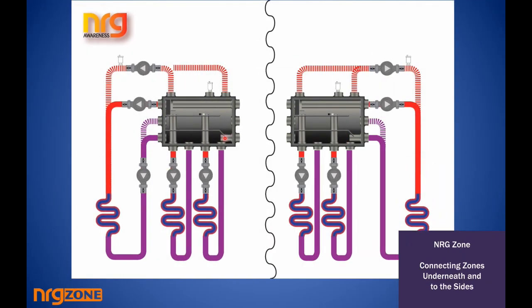So if we take it now that we have zones, if we have our heat coming in at the right hand side here into R1 and coming back from say R3, we can then take zones from this point over to a pump from T3. You could actually take it from T2 if you have a vent on T2, but you pump towards the vent, you never put the vent behind the pump. And you can also take it from T1 through a pump and you pump towards the vent. So now you're delivering down to a zone here.